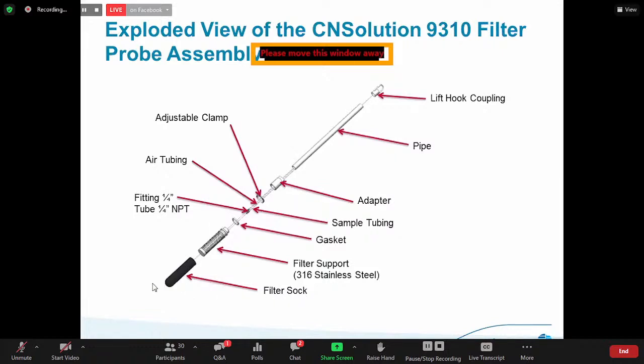It's a membrane that slips over this housing here. And down this tube are 2 lines. One is for pulling the sample. The other one is for injecting pressurized air into this assembly, thereby pushing off the slurry that might be covering the filter. And then once that pressure is relieved, the liquid flows into this support.